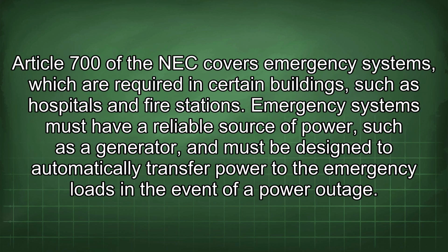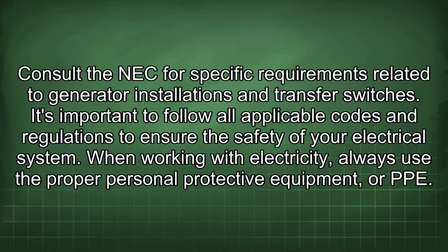Article 700 of the NEC covers emergency systems, which are required in certain buildings, such as hospitals and fire stations. Emergency systems must have a reliable source of power, such as a generator, and must be designed to automatically transfer power to the emergency loads in the event of a power outage. Consult the NEC for specific requirements related to generator installations and transfer switches. It's important to follow all applicable codes and regulations to ensure the safety of your electrical system.